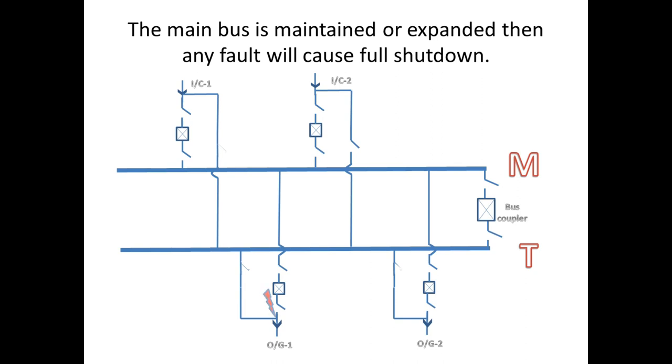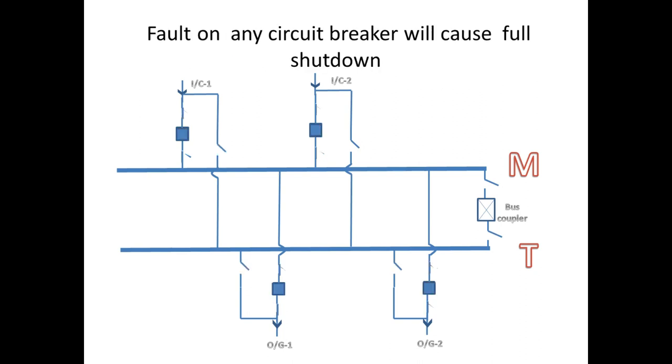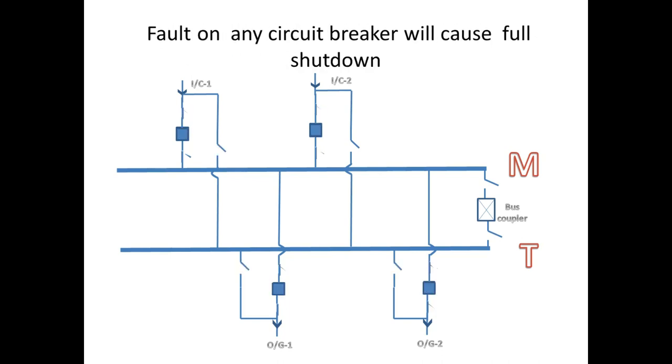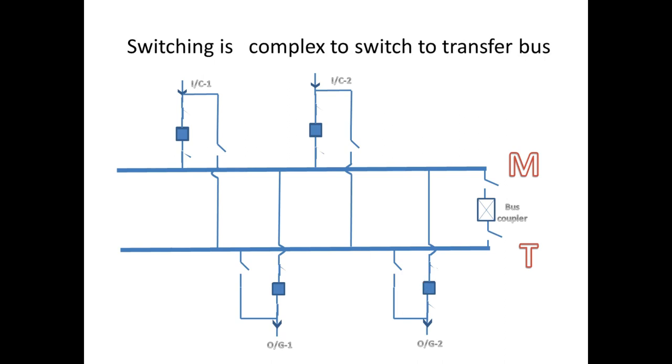Second, a fault on any of the buses or any circuit breaker could cause complete shutdown of the whole substation. Third, switching is somewhat complicated when maintaining a breaker.